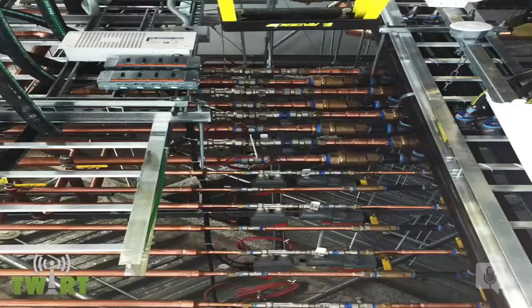Just some of the pumps as they were being set up. What we also did above the top, you'll see some green flashing lights if you look up above the transmitters on the active ones. We have energy valves on it. These modulate the water. We keep the delta from inlet to outlet temperature of 10 degrees so that we're not wasting water up on top.